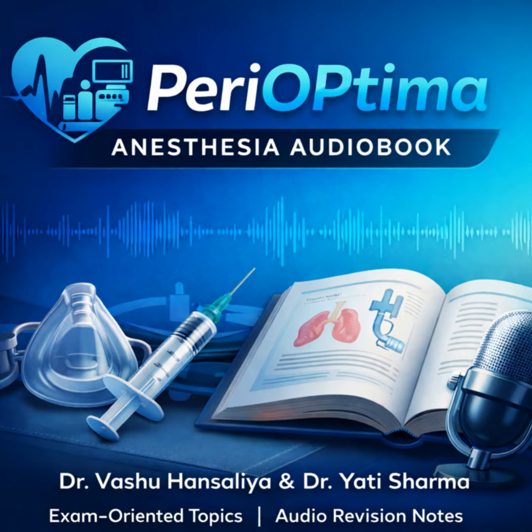Okay, the structure is complex, and it's complex for a reason. It has to ensure unidirectional flow through the absorber. So number 1, the inspiratory and expiratory limbs. These are just the large bore corrugated tubes connecting the patient to the apparatus. And the corrugations are there to reduce kinking, and the large diameter reduces resistance.